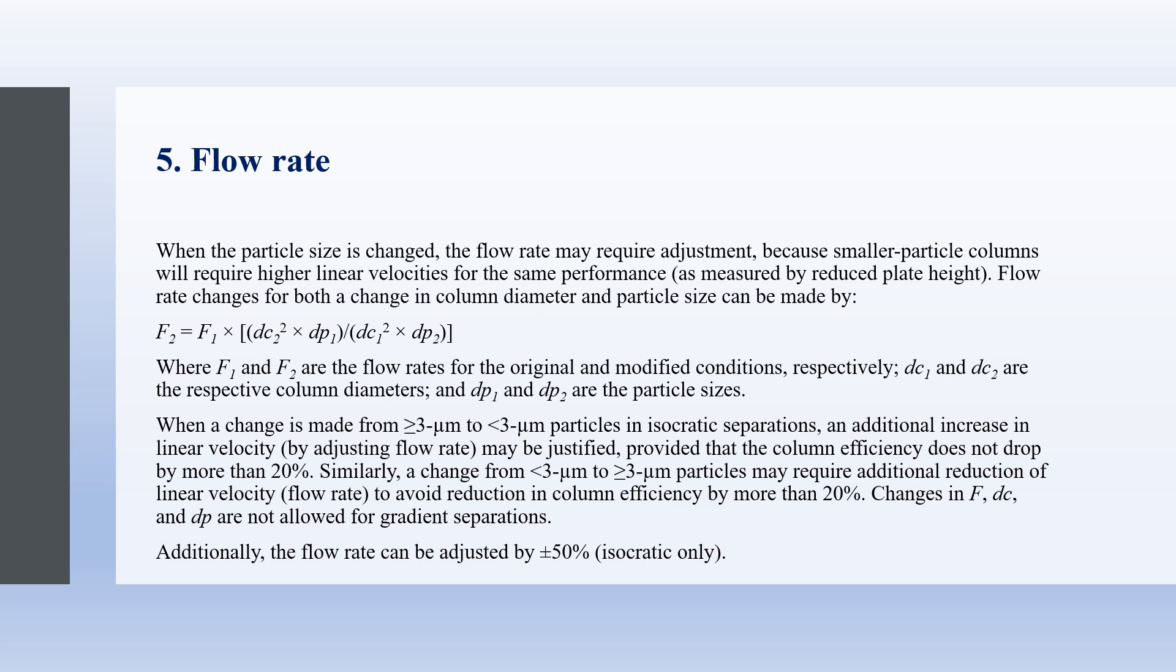So when you are changing the column, it's necessary to look at the particle size and adjust the flow rate appropriately. But as you adjust the flow rate, it's necessary to ensure that the column efficiency does not reduce by more than 20%.